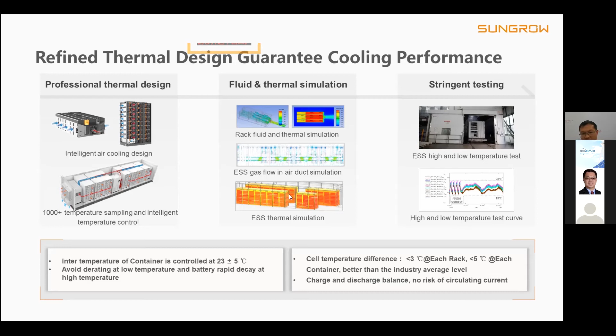The first is for the battery container. We adopt high pressure BMS, and the BMS will record the status of the battery module and battery rack. This means information such as voltage, current, SOC, SOH, and temperature will be recorded and monitored and submitted to the SCADA system. The second is DC cable detection.